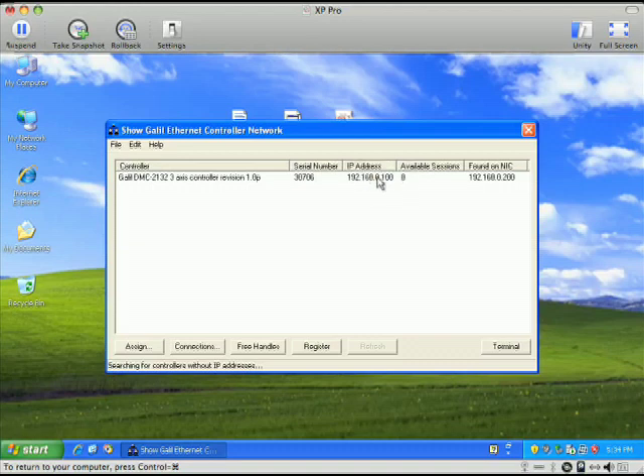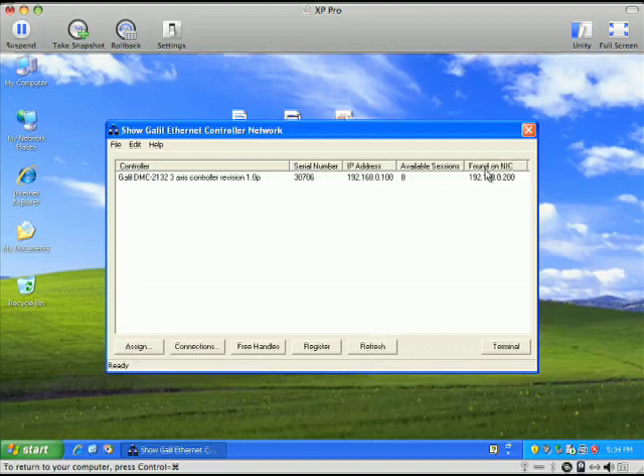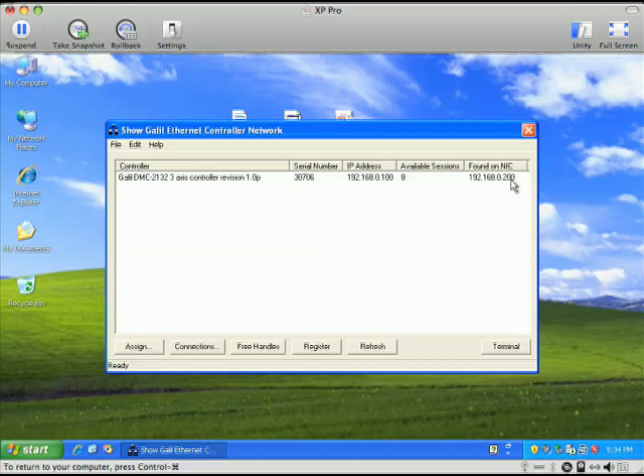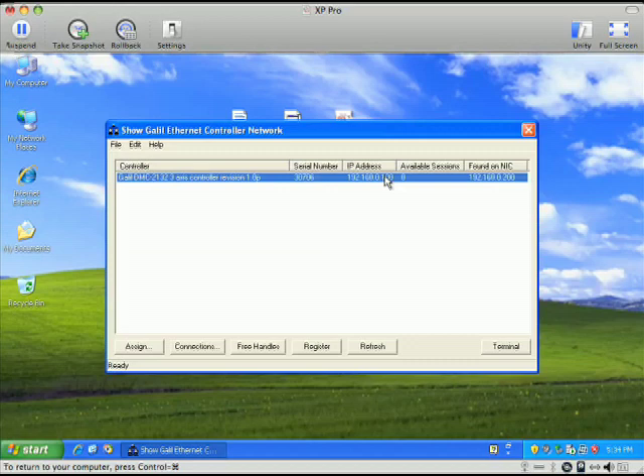You can see my IP address is .0.100, and found on NIC. In other words, this is the network card that we just set up with that .200, and the .100 is the address of your actual controller. So we can see that it did communicate with it correctly. If you don't see this line, then something's not right with your Ethernet cable or the way the network was set up.